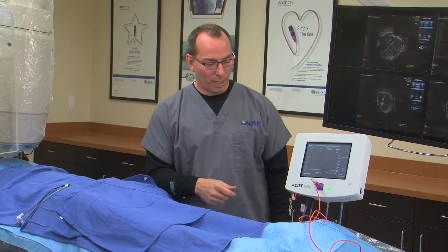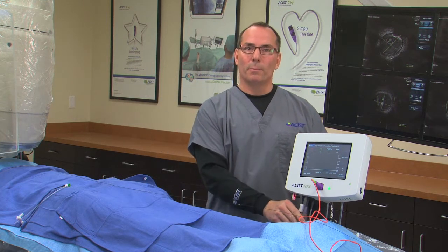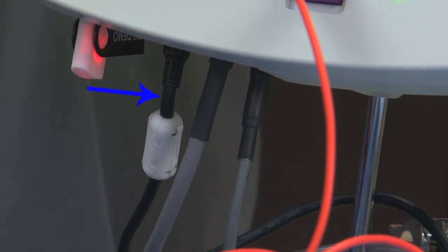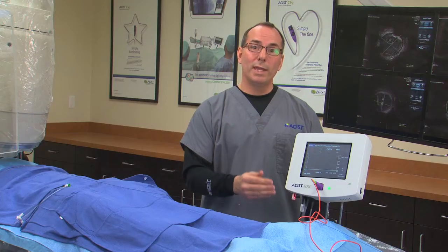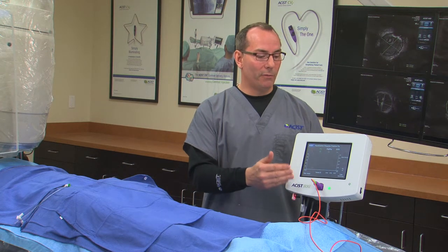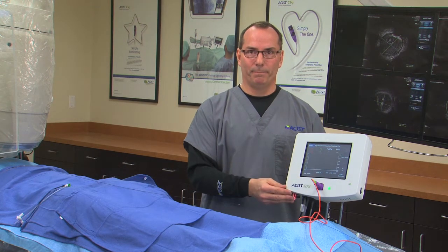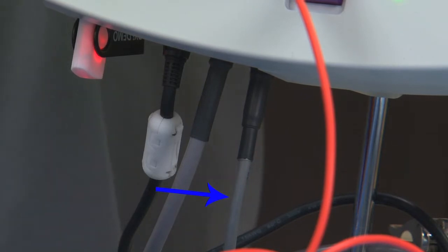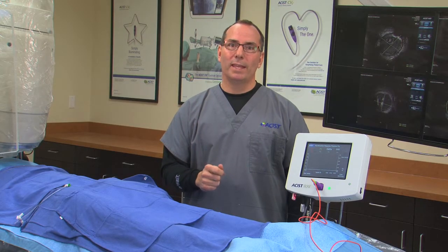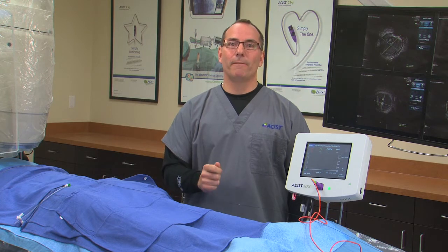The Rxi Console has three cables on it. The power cable, which supplies the unit with power. The second cable brings the patient's aortic pressure into the console for FFR calculation. So then we can see the pressure waveforms of the patient on the system. The third cable is actually for exporting the Navvus catheter pressure into the cath lab hemodynamic system. This becomes important when the cath lab Hemosystem has the FFR software.